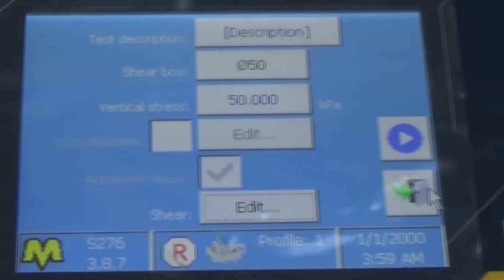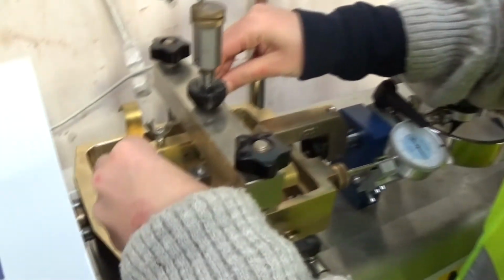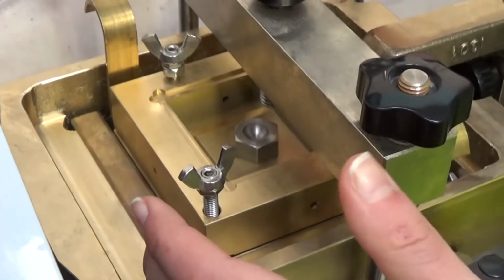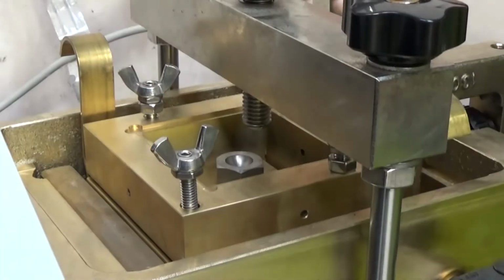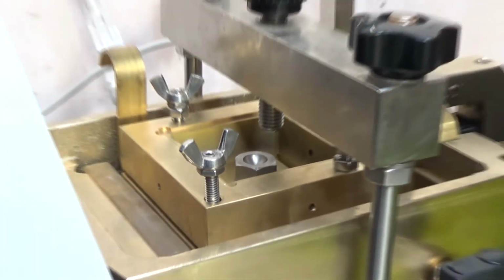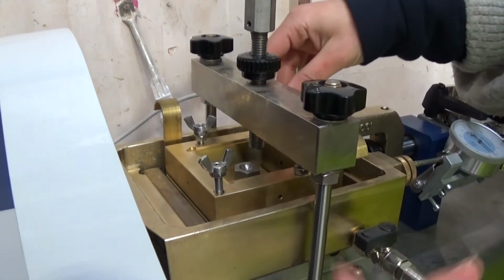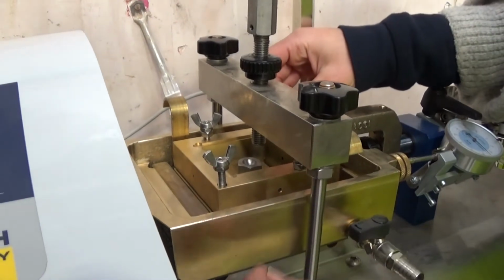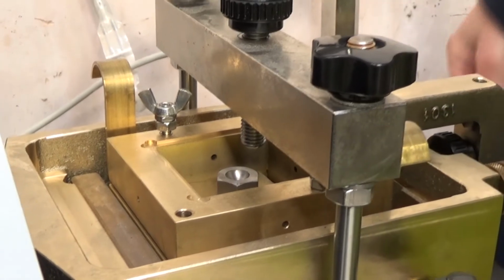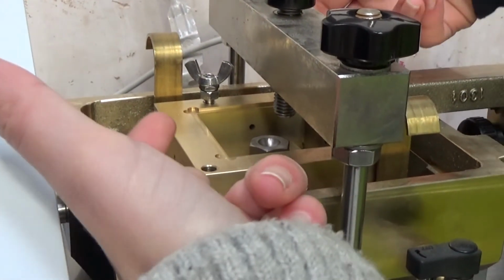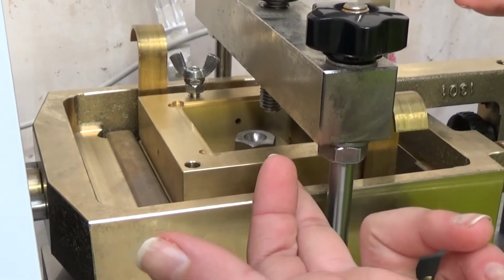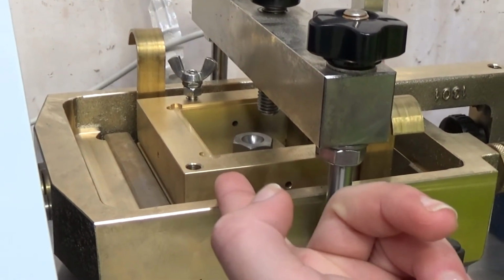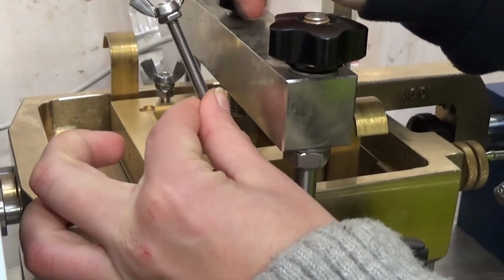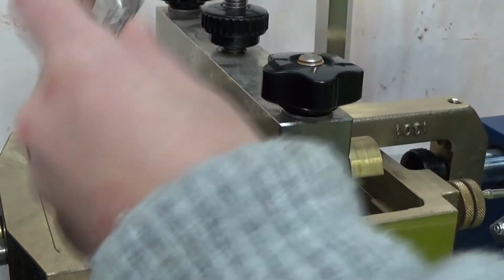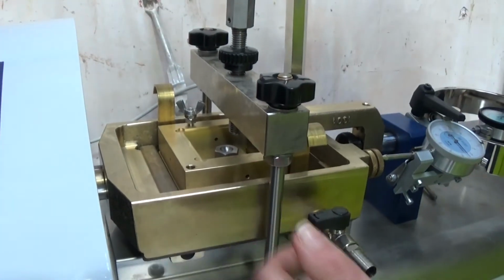Okay, so the very important thing is that during the consolidation, after the preparation of the sample, you will have this nut fixed, because the two parts of the shear box need to be fixed, put together. But when the shear phase starts, it's very important to remove the nuts, because the shear box must be able to move, and the sample could be sheared. If you forget to remove this, something like this happens, the nuts will be damaged, and the test fails for sure.